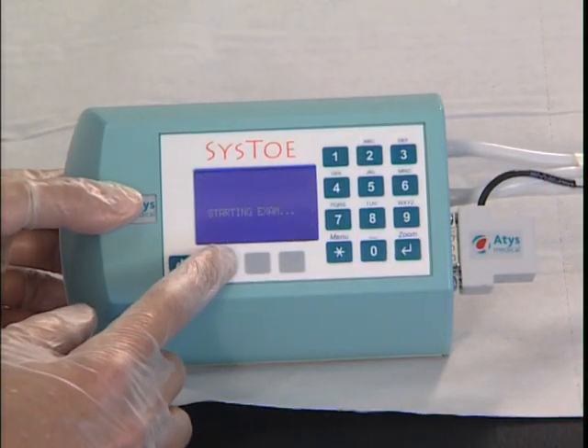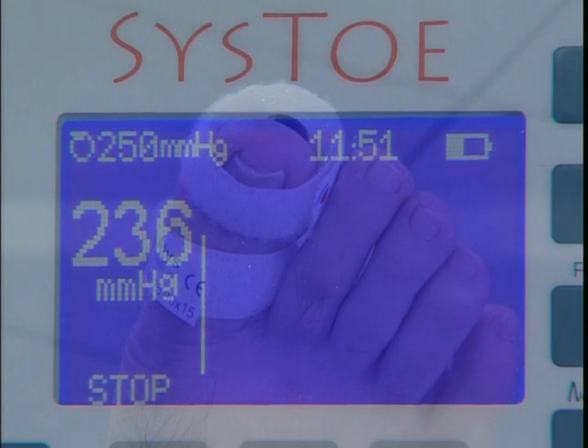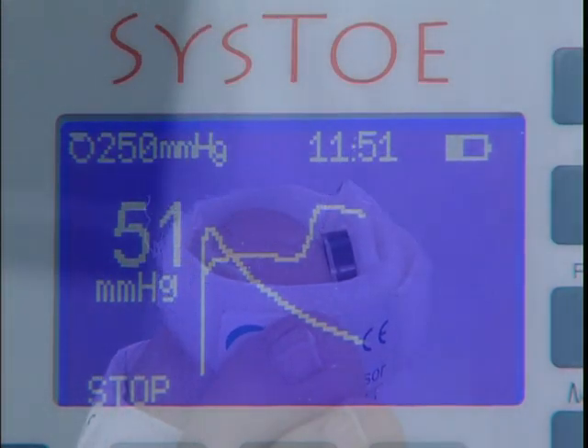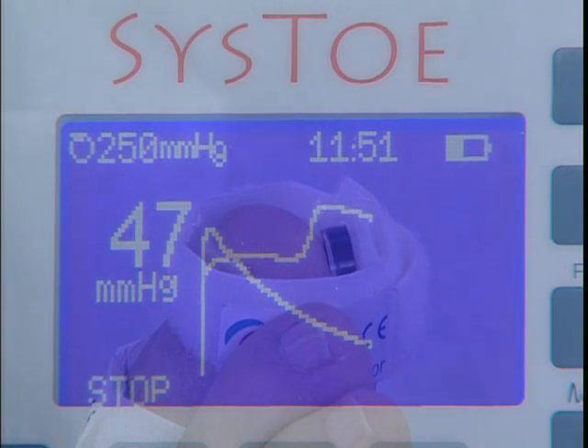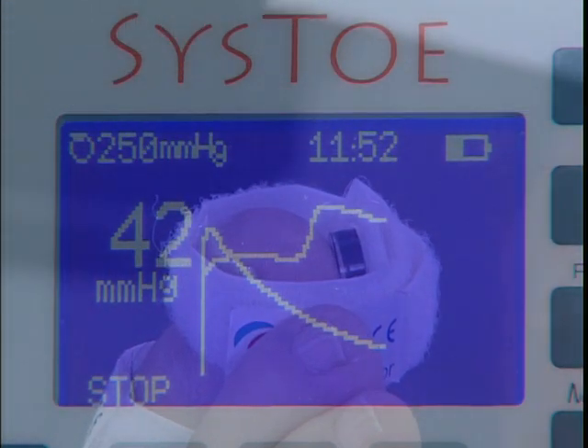Start the measurement by pressing the start key. The occlusion cuff automatically inflates to a preset pressure, in this case 250 mm mercury. Once the target pressure has been reached, the cuff automatically deflates at a steady rate. The SysToe precisely measures the cuff pressure at which arterial blood flow resumes, as detected by the sensor. This is the systolic blood pressure. At the end of the procedure, the toe's systolic pressure is displayed on the screen.